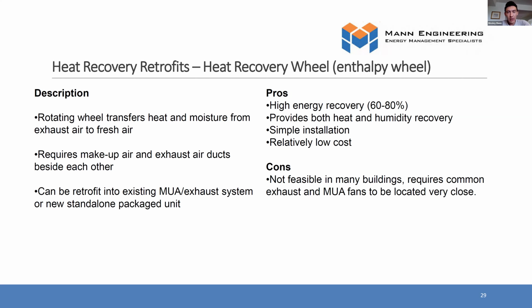The next heat recovery option we'll talk about is the enthalpy wheel. They also call it a desiccant wheel. Basically, it recovers both heat and moisture, which we call latent heat. So it has very good energy recovery, like 60 to 80%. One of the main downsides is that it's very dependent on the system layout. If you have a central makeup air unit and exhaust fan right next to each other on the roof, perfect. It could be a great candidate.